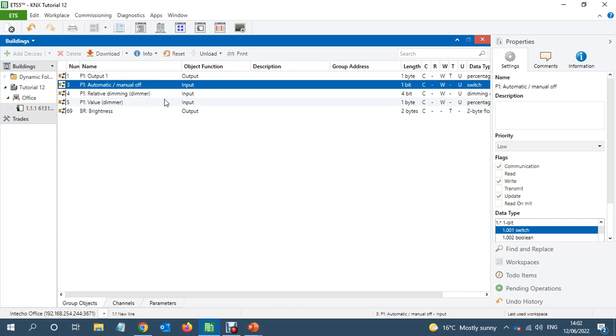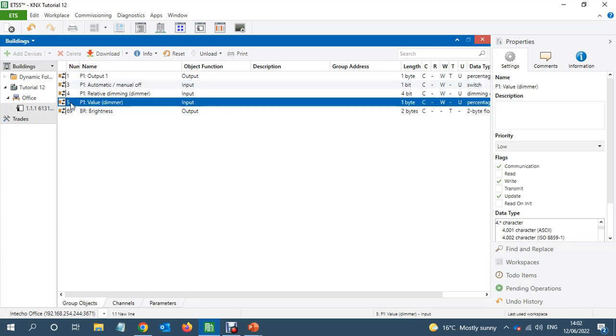So in case you got an office where you got the PIR which is maintaining 500 lux, someone thinks okay 500 lux is not enough and they want the light to be turned on 100%. They send 100% value to this object, it will disable PIR for one minute, for one hour, and the light will stay on 100%.